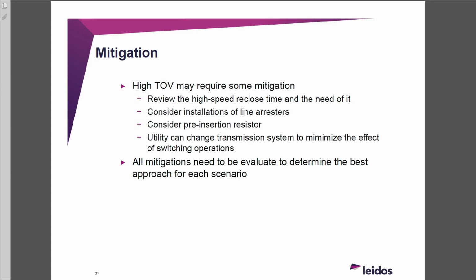If you do a couple different locations, it depends how big your system is, it might be too big, spread all over the place. So you grab a couple loops in the north section, the south section, and then you start reducing to see, okay, I reduced 75% and we still have an issue, I have a lot of lines like that, good luck. But if I reduce 5%, I'm at 95%, I'm good, I do 9, I'm even better, so I can start feeling more comfortable with the results. I would grab different loops of your system, depends how big it is.